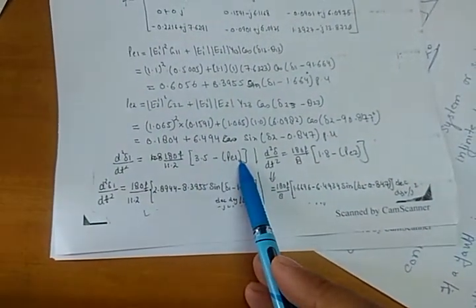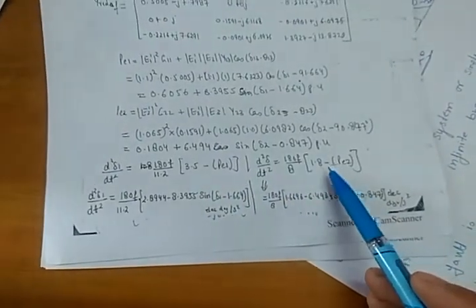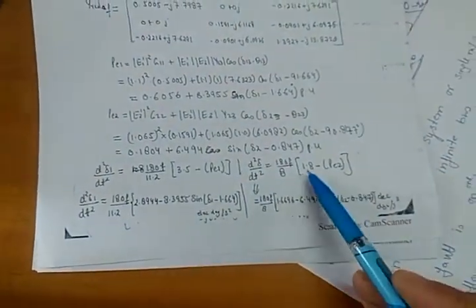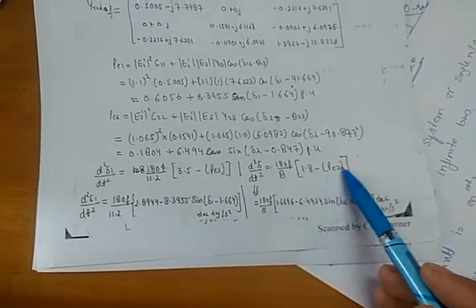And after the fault, P electrical 1 and P electrical 2 will change. So you will have P mechanical 1, 3.5, minus P electrical 1, and you will get this. This is during the fault, and after the fault you will have P mechanical 1.85 minus P electrical, so it will come out to be this. So this is the angular acceleration. Angular acceleration. Yes. Okay. Here I have calculated the formula for when the fault is cleared, that is, Y reduced after fault.